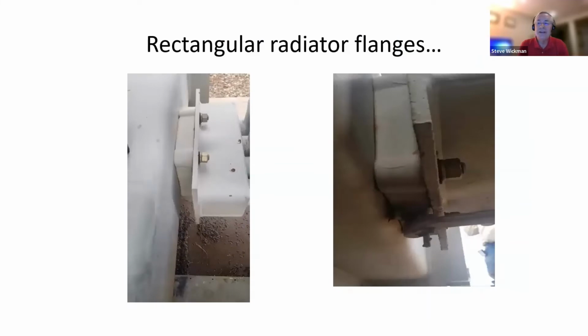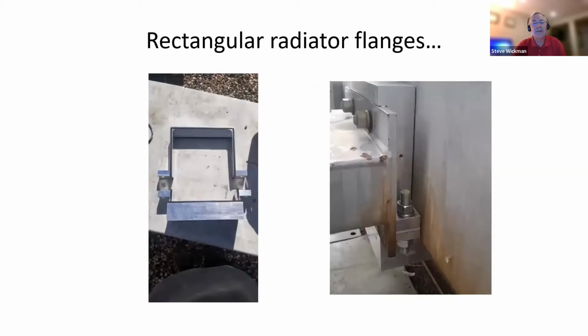Another interesting challenge is some of these smaller transformers. This was on a 34 to 12 or 34 to 4, probably a 6250, 5000 kVA type transformer, where the radiator flange is in a rectangular type configuration as opposed to round. There's not enough work clearance to get in and do the drill and inject. That's not an effective solution here. So we were able to fabricate a clamp to get around the back side there, fill that with sealant compound, and effectively contain the leaks on that guy.